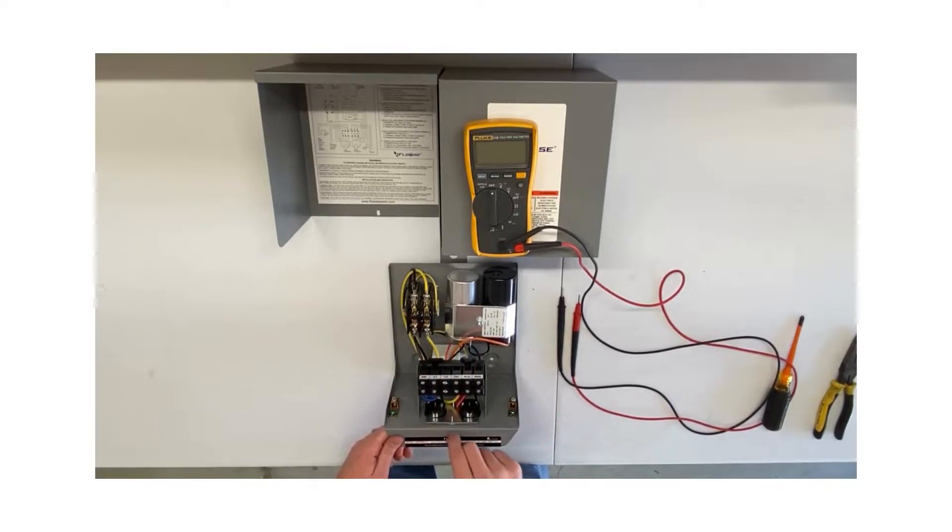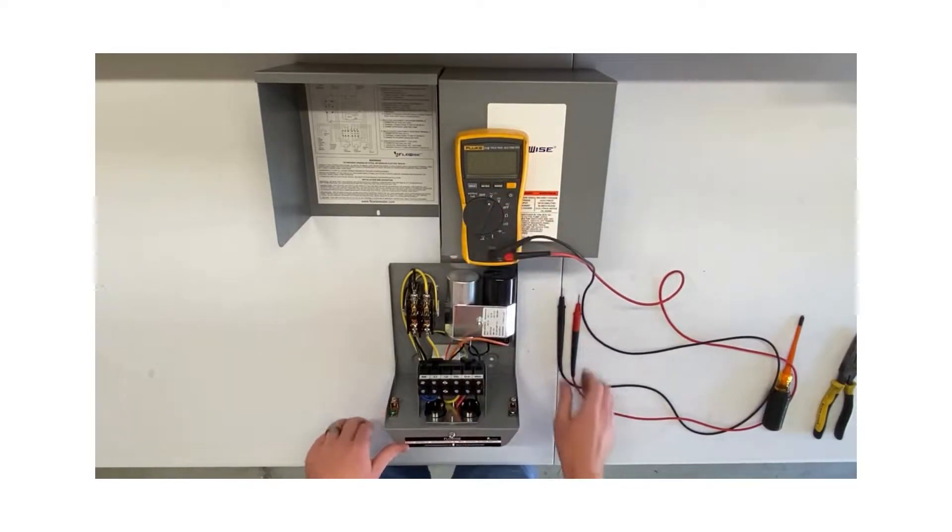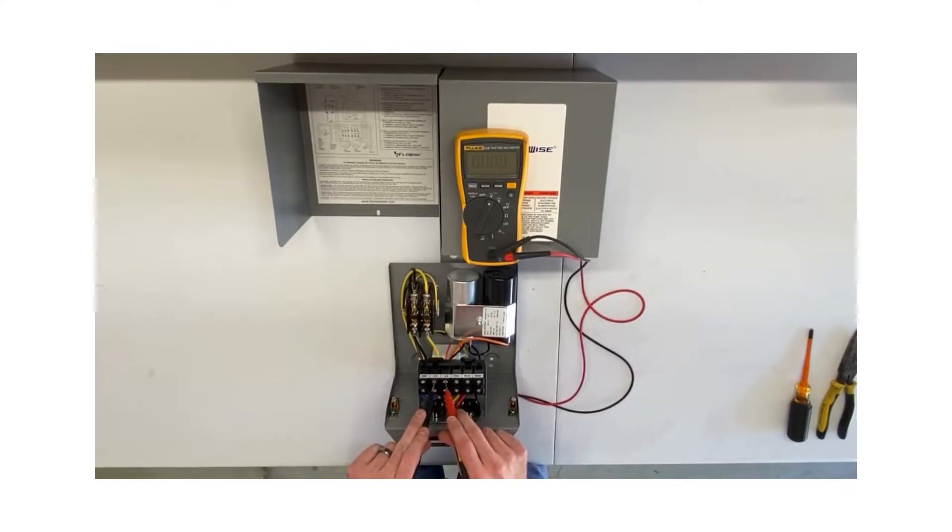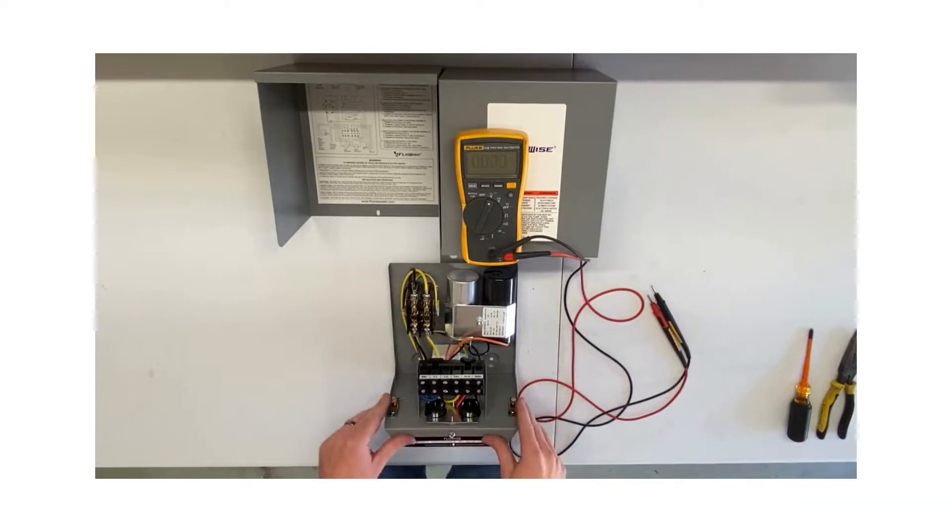After you have turned it off at the breaker, go ahead and take the cover off the box. I like to take the screw that holds the lid on and put it back into the base of the box so I don't lose it. Once I have the cover off, I'm going to take my multimeter, set it to AC volts, and check L1 to L2 and ground to L1 and L2 to make sure I don't have any voltage. That way I know I'm safe to test inside this box now.